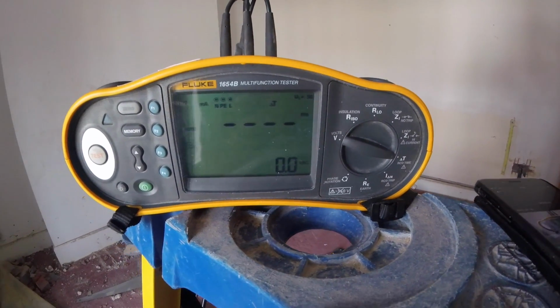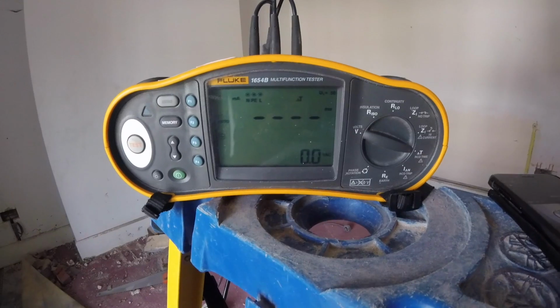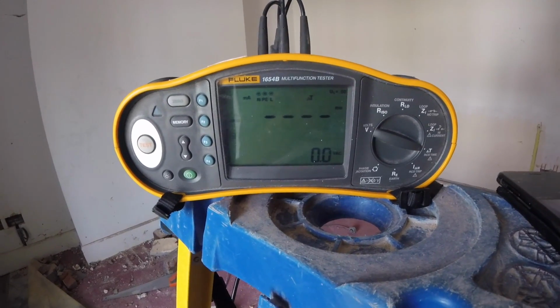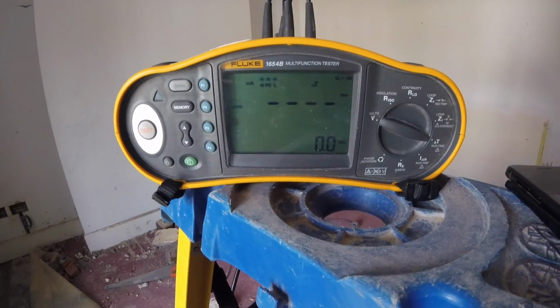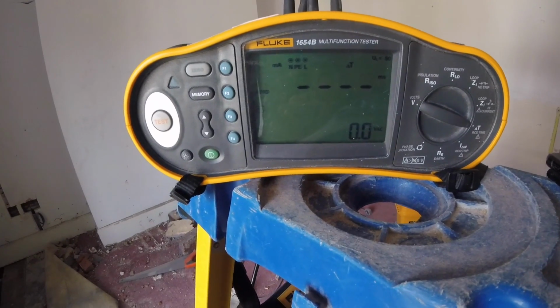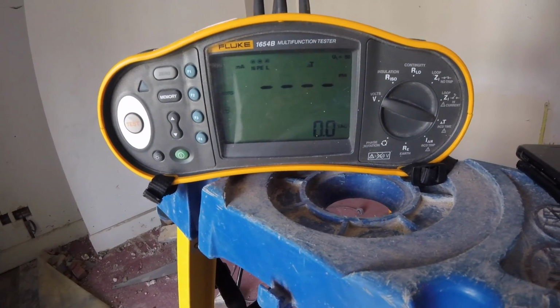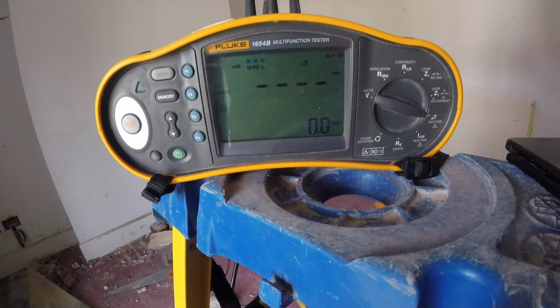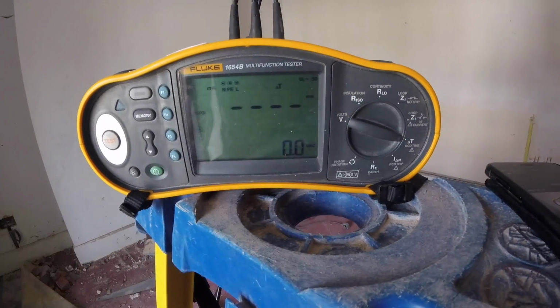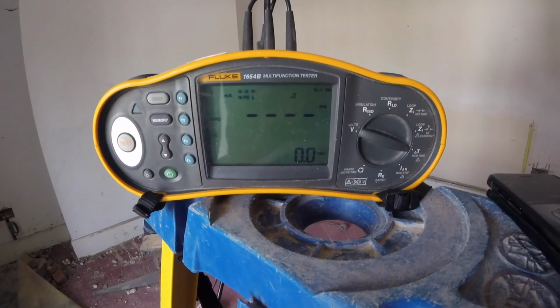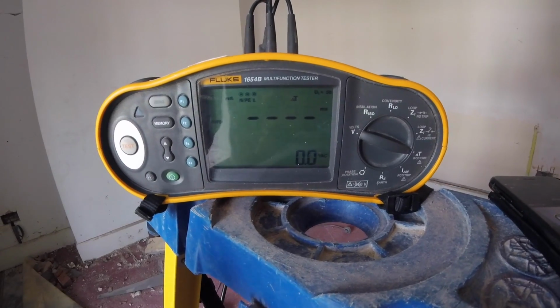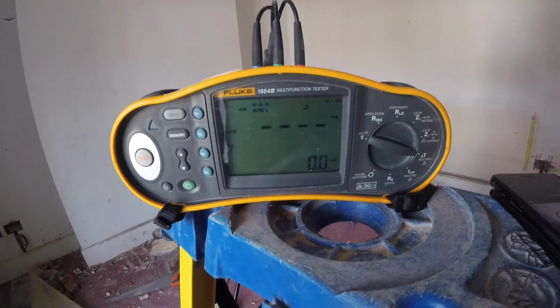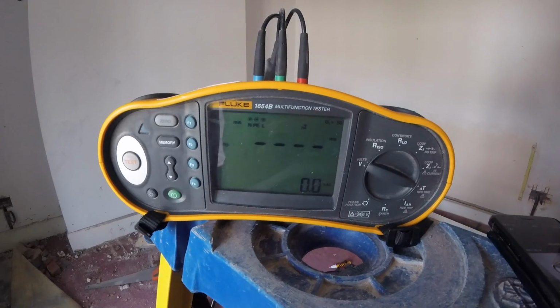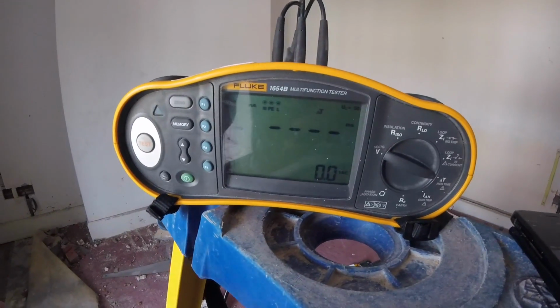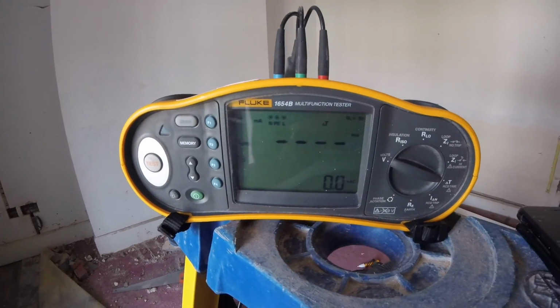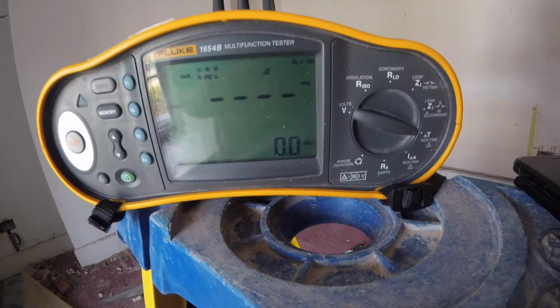That means, say if you're working in a commercial building where the fuse board is miles away from the circuit you're testing, and you want to test right at the end, you don't exactly have to stay with the meter. You can plug the meter in somewhere and stay at the fuse board and flip the trip up every time it trips it. Or likewise, if you're at the fuse board and you clip all 3 probes onto the terminals needed, you can just press auto, and then all you need to do is flick the breaker up every time it trips it. So yeah, quite good.